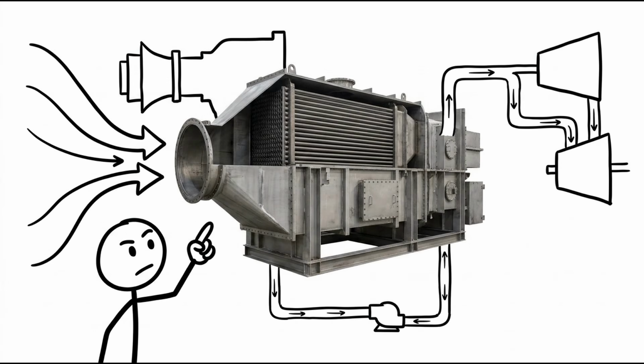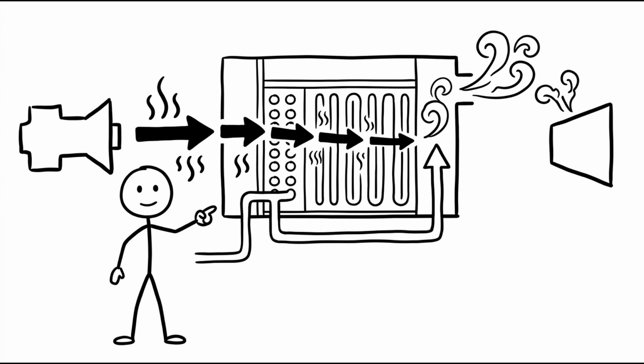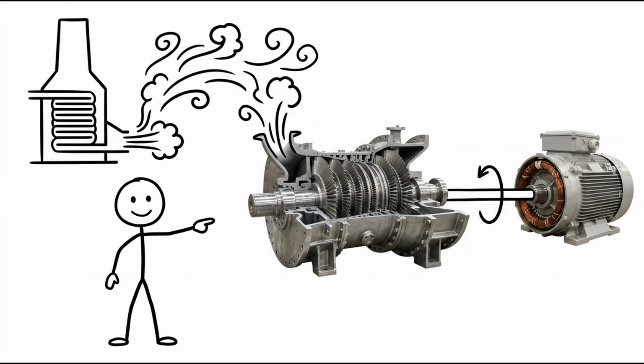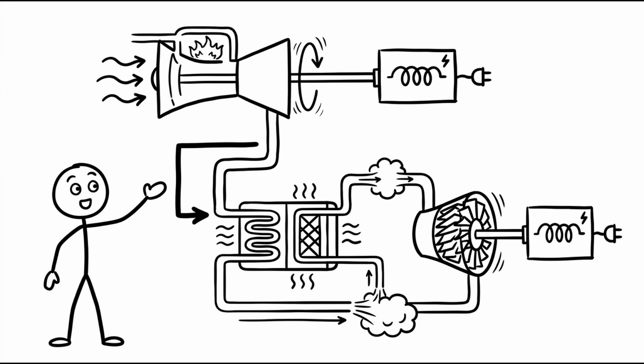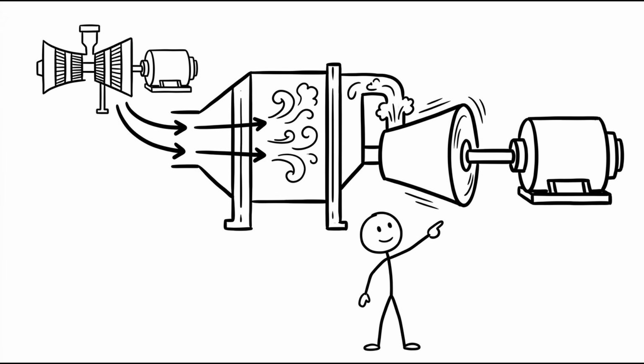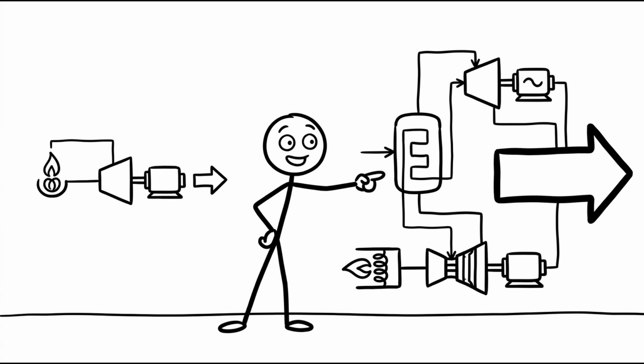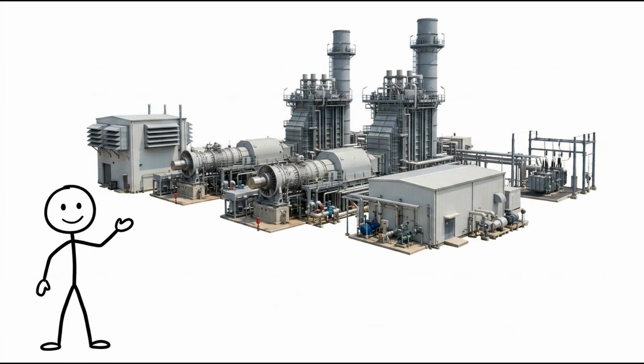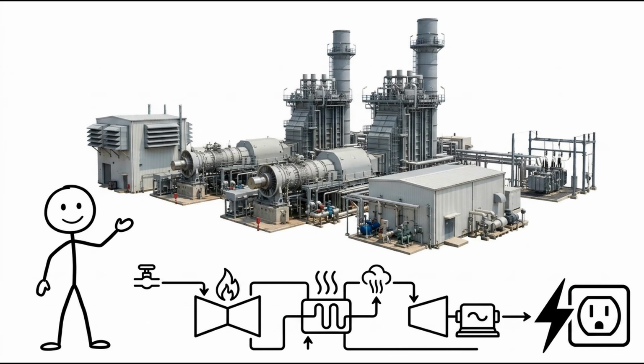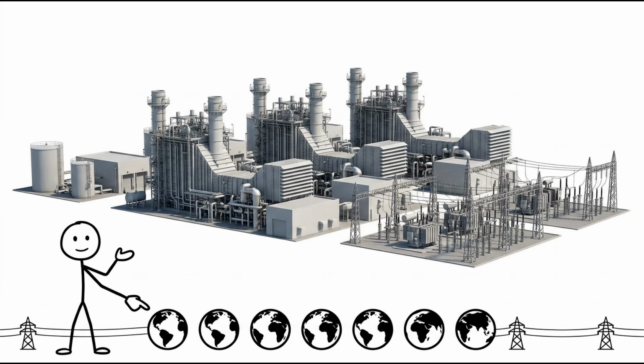Instead, the hot exhaust passes through a heat recovery steam generator, often called an HRSG. This system captures the remaining heat and uses it to produce steam. The steam then drives a second turbine connected to another generator. By extracting energy from the same fuel twice, first through the gas turbine and then through the steam cycle, a combined cycle plant can achieve much higher efficiency than a simple combustion system. This is one reason natural gas combined cycle plants have become an important source of electricity in many countries.